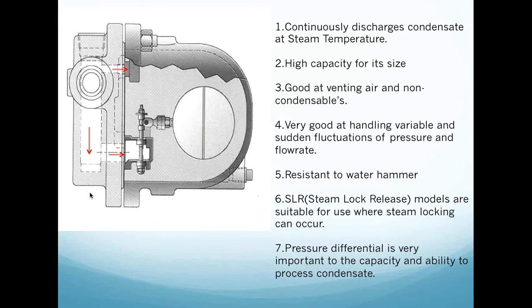These traps are very, very good at low pressure differentials in processing condensate. So on a large heat exchanger, this would be a device that I would look at first, only because I know that in heat exchangers, as the temperature is being satisfied by the product because of the steam we're putting into the heat exchanger body, I'm going to degrade my pressure differential, and I have to have a trap that is capable of passing the condensate as it's formed. Many times it's a very good amount of condensate at a very low differential, and this particular trap can do that.